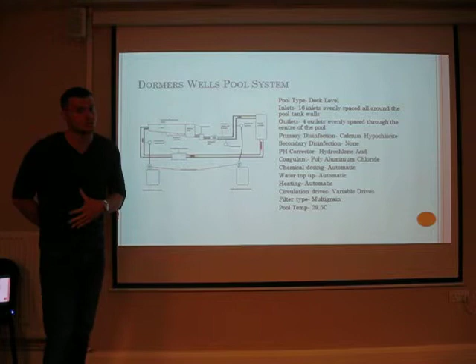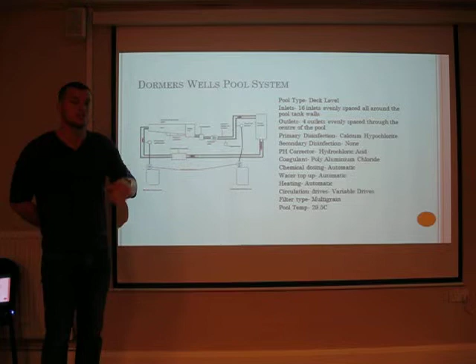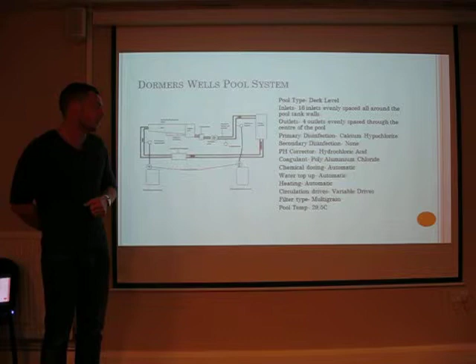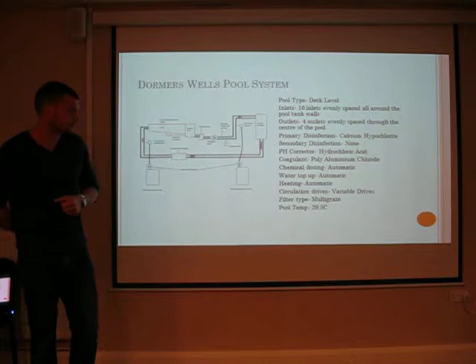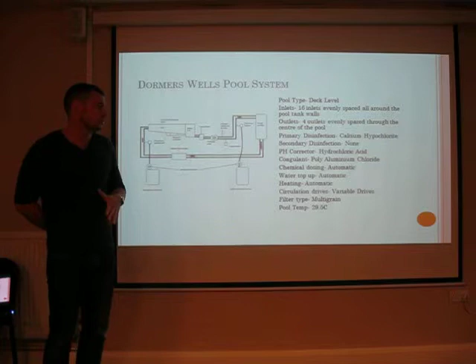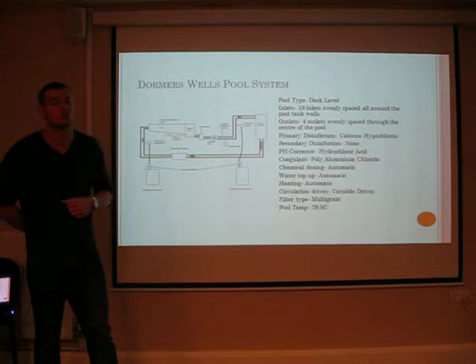The Dormers Wells pool system is a deck level pool with 16 inlets evenly spaced around the poolside tank, and 4 outlets evenly spaced through the centre of the pool from shallow to deep. The primary disinfection is calcium hypochlorite, with no secondary disinfection. The pH corrector is hydrochloric acid and the coagulant is PAC. The dosing unit, water top-up, and heating are all automatic. Circulation drives are variable, filtration is multi-grain, and the temperature is kept at 29.5 degrees Celsius.